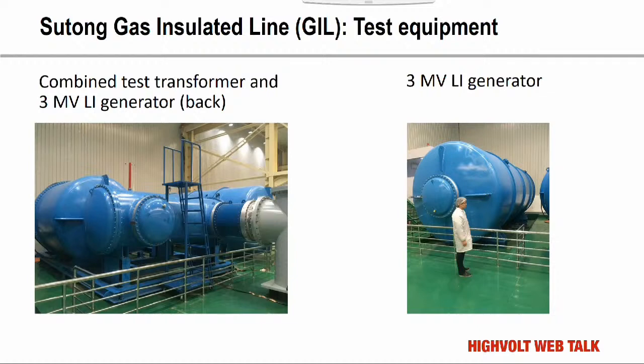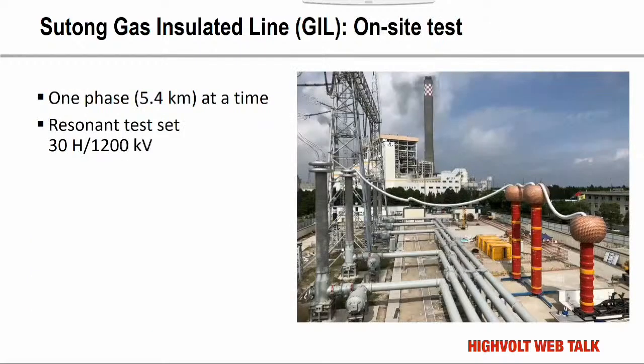If you go to the next slide, site testing is something completely different. We test one single phase of this 5.4 kilometer GIL at once. Here you see the resonant test set required to do that, with 30 Henrys at 1200 kV, a very large one that has high power but a very low duty cycle.